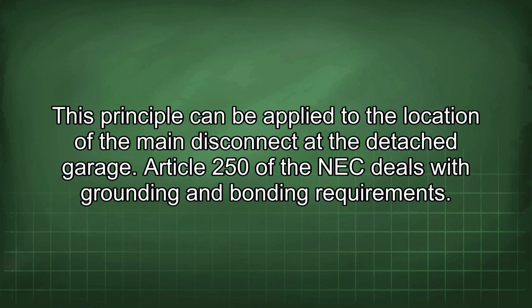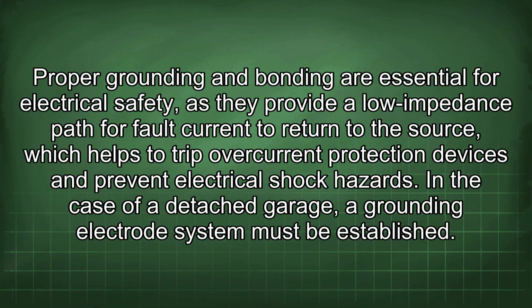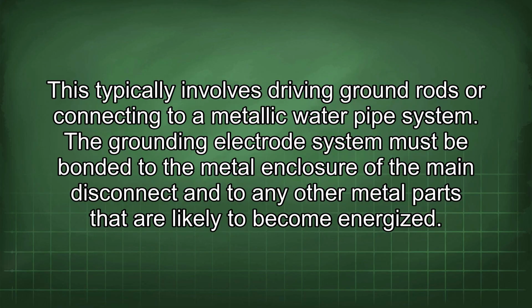Article 250 of the NEC deals with grounding and bonding requirements. Proper grounding and bonding are essential for electrical safety, as they provide a low impedance path for fault current to return to the source, which helps to trip overcurrent protection devices and prevent electrical shock hazards. In the case of a detached garage, a grounding electrode system must be established. This typically involves driving ground rods or connecting to a metallic water pipe system.